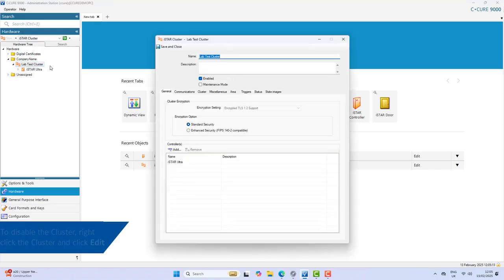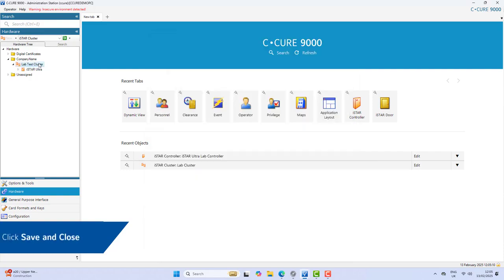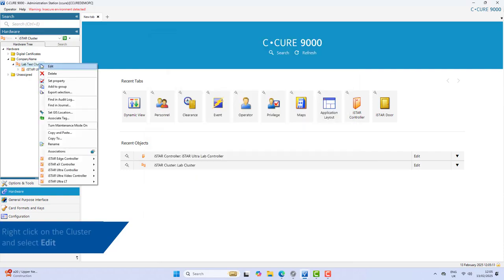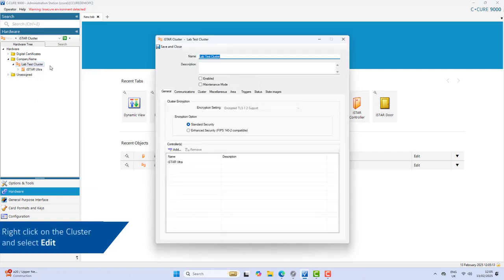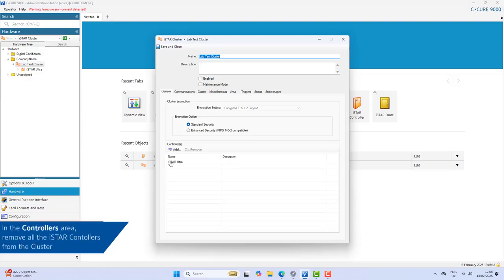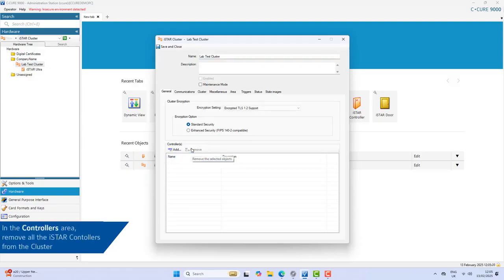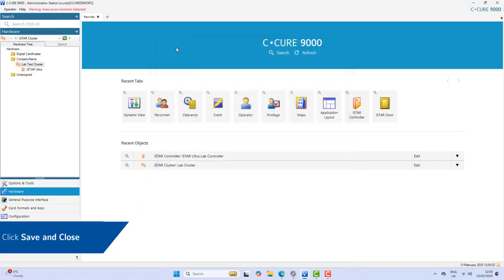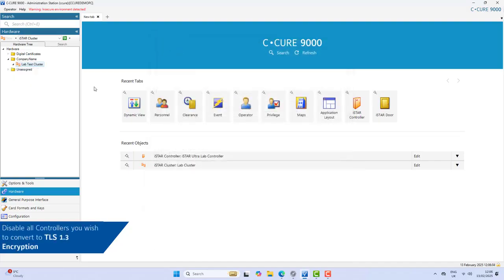Right-click the cluster and select Edit, clear the Enable checkbox, and then click Save and Close. Right-click on the cluster and select Edit. In the Controllers area, remove all iStar controllers from the cluster, then Save and Close.